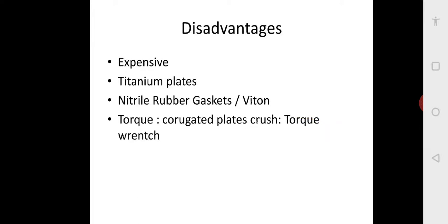Disadvantages include the initial cost being very expensive. Even titanium plates can be used, adding to cost. The gaskets are not ordinary natural rubber but high quality synthetic rubbers. Proper torque must be applied during tightening because the gap is very small — a proper torque range must be used for assembly and disassembly.